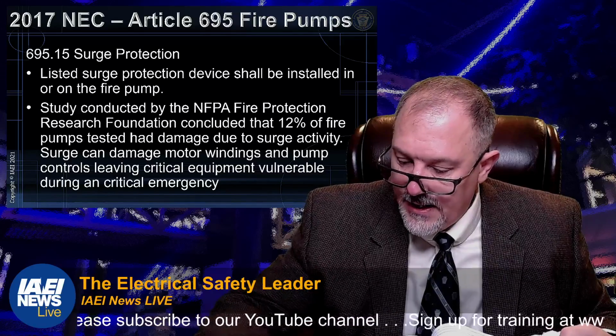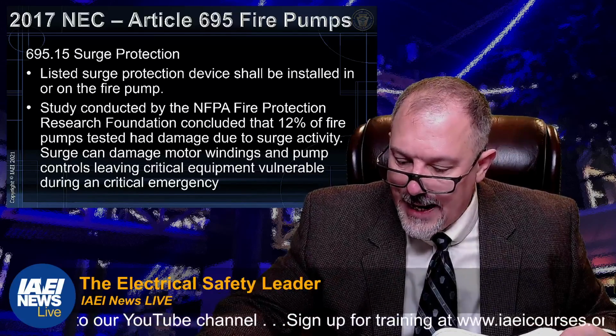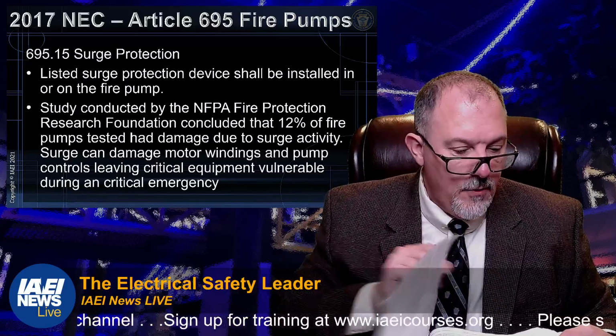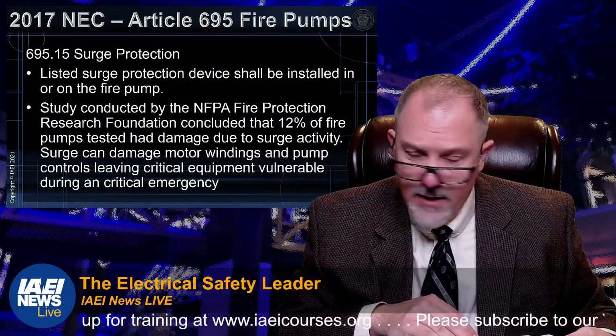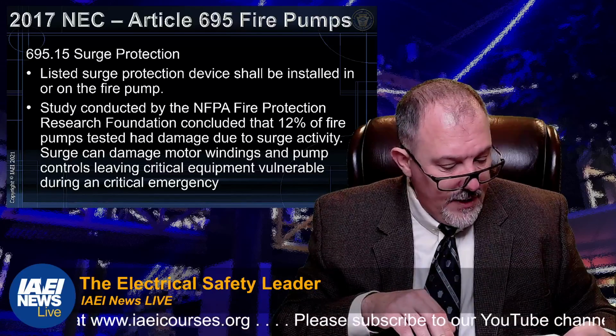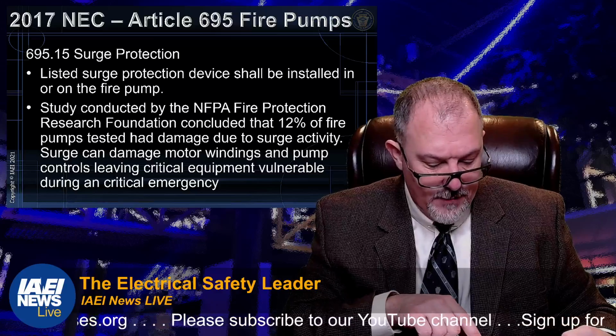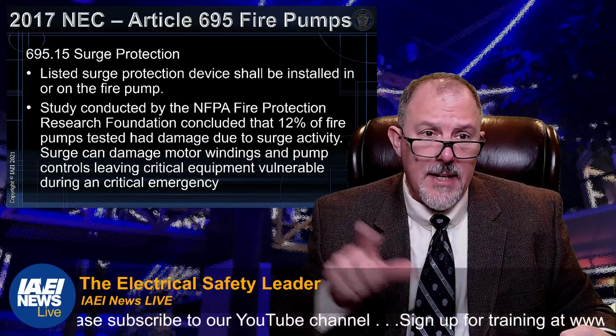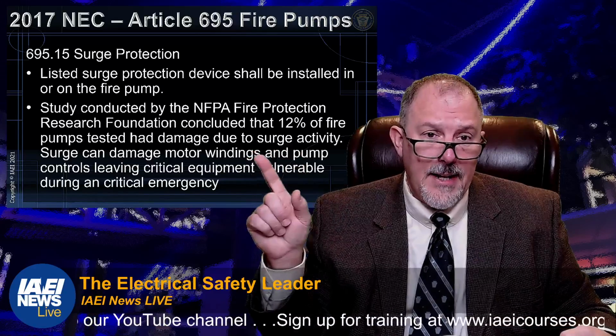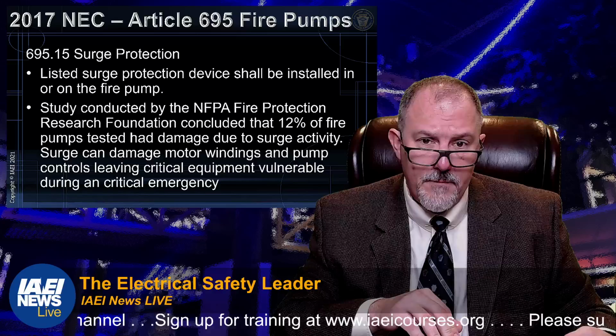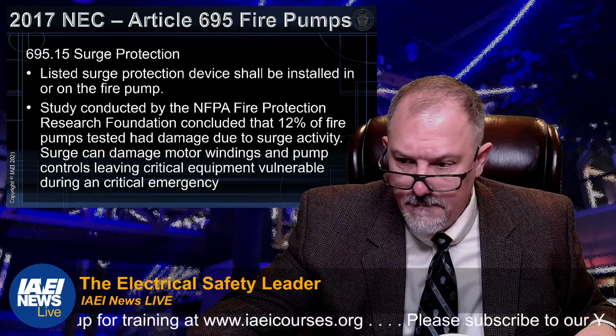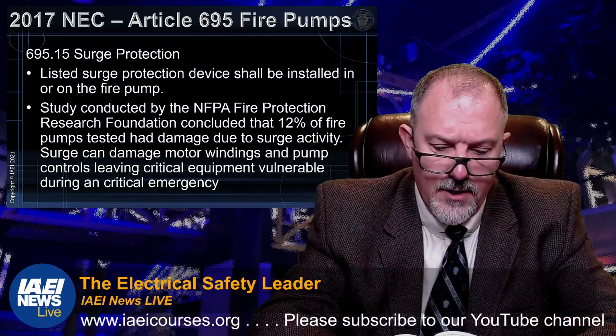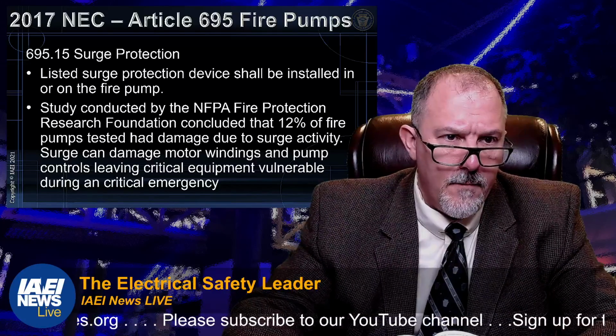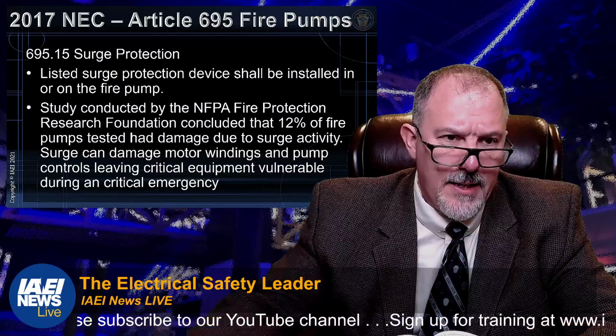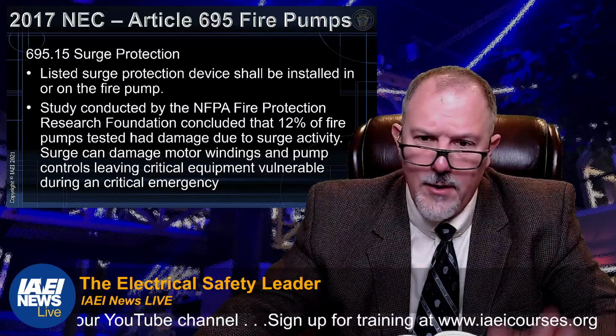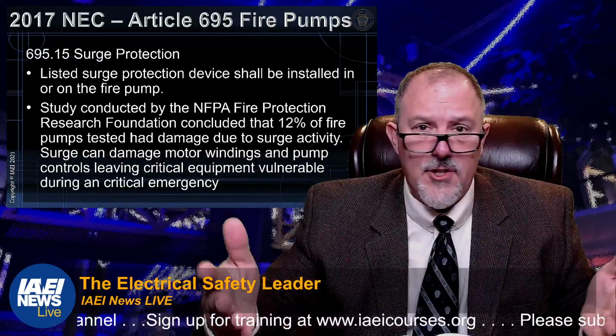695.15. 695.15. Mark your books. Tab them. Because these will escape you if you don't remember. 695.15. Surge protection. A listed surge protection device shall be installed in or on the fire pump controller. This was added in the 17 code based upon a study conducted by the NFPA Fire Research Foundation. And you can get those studies. If you just go to the Research Foundation website. So you can Google half of these or search half of these, using any search engine that you use.